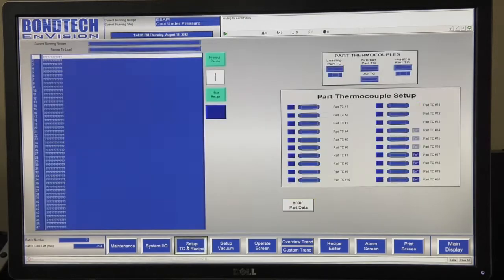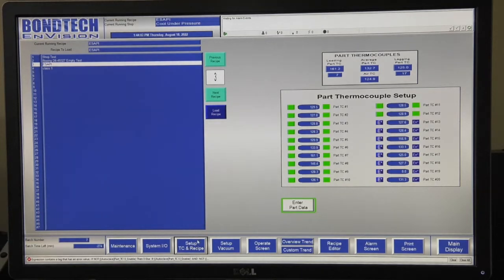And also the flashing down here is showing whether or not each individual vacuum transducer is active. The setup TC and recipe, that is the setup thermocouple and recipe page. Here's where you can actually go through and choose which recipe you want to load for that particular cycle or that product that you are running at that time.